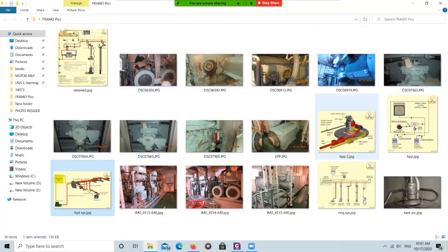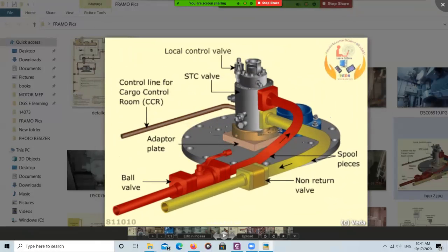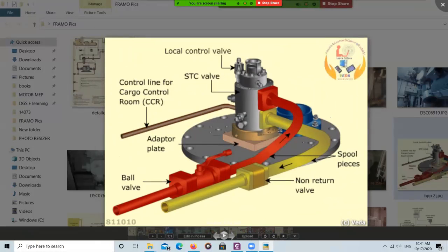The speed torque controller is located on the tank dome and is used to control the pump — basically you are controlling the RPM of the hydraulic motor. The hydraulic motor is also a variable displacement axial piston type. The automation signal coming from the CCR is the remote signal, and the local control valve is used during tank stripping. The red line is the high pressure hydraulic line and the yellow one is the return line.